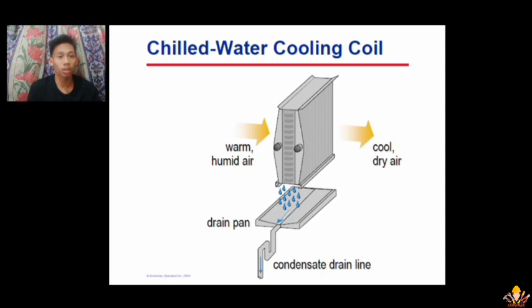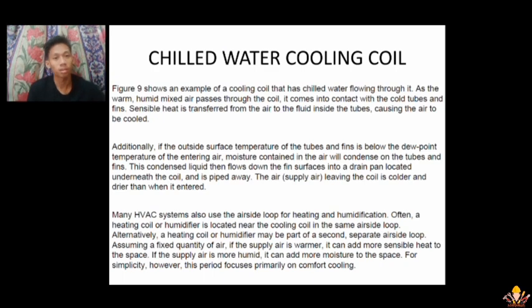Another component is the chilled water cooling coil. Figure 9 shows an example of a cooling coil that has chilled water flowing through it. As the warm, humid mixed air passes through the coil, it comes into contact with the cold tubes and fins. Many HVAC systems also use the airside loop for heating and humidification. Often, a heating coil or humidifier is located near the cooling coil in the same airside loop.